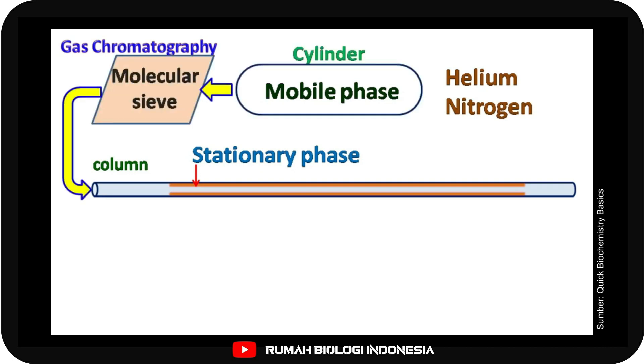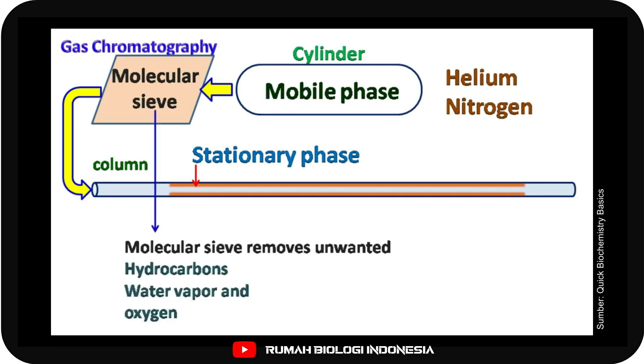The mobile phase gas is kept in a cylinder which is connected with the column via molecular sieve. The molecular sieve separates the unwanted hydrocarbons, oxygen and water vapor that may interfere with the test sample during analysis.